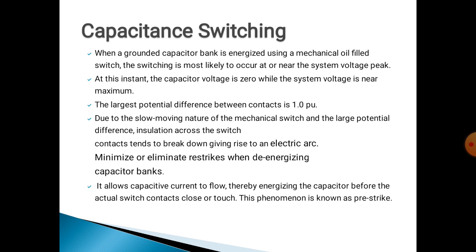In that particular condition, the current leads the voltage by 90 degrees. When the switch opens, the capacitor is isolated from the supply and remains charged. When the capacitor tries to retain its maximum charge, the voltage across the switch reaches the peak value of 2 pu, which is potentially dangerous to the circuit.